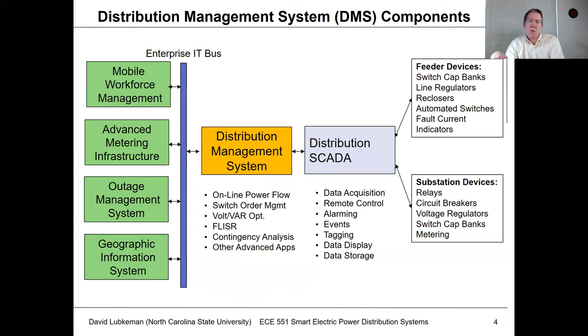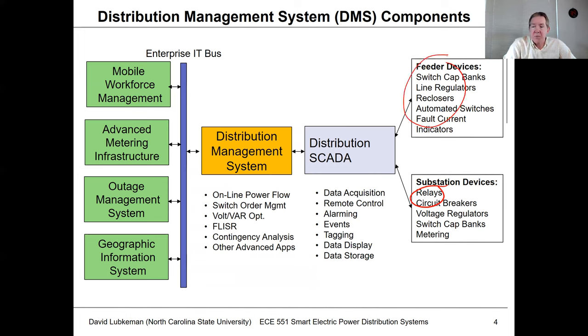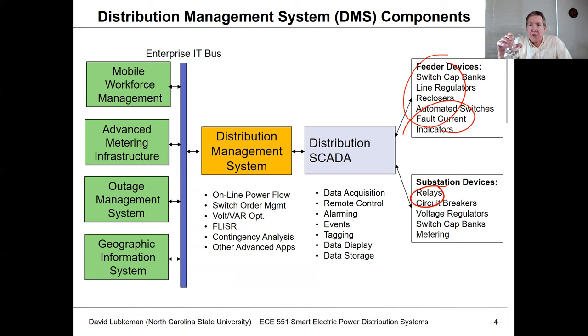Built on top of SCADA, the SCADA system links up to all the devices in the field — polling circuit breakers, relays, and voltage regulators and getting all state measurements associated with the substation. You also have the ability to get data from feeder-level devices, such as reclosers, switched capacitor banks, line regulators, and fault current indicators. SCADA pulls all this information together and gives you an indication of what's going on in your system.